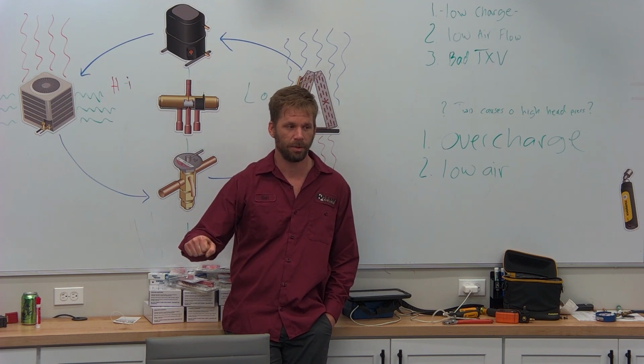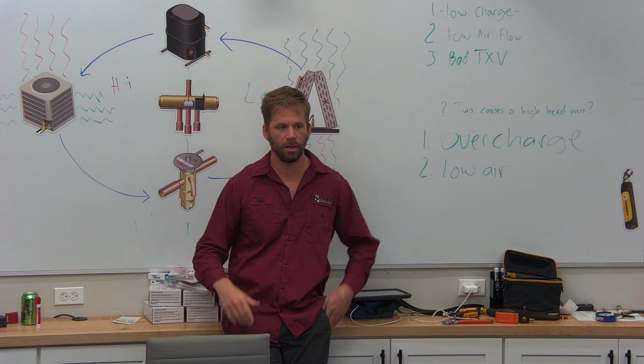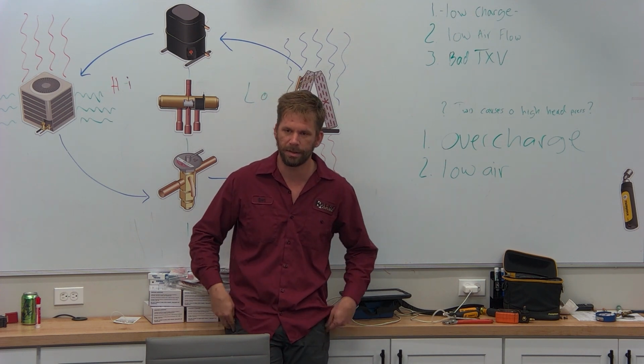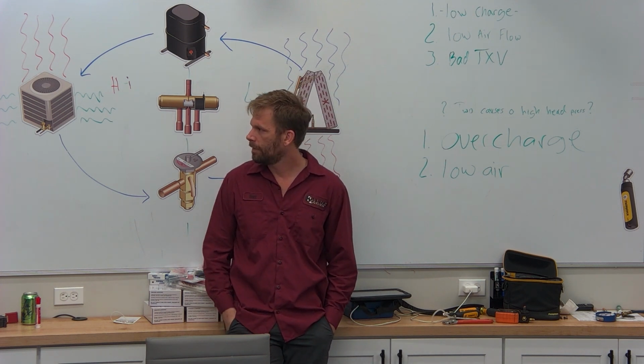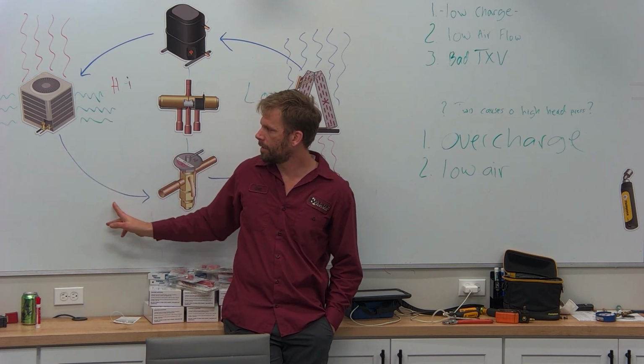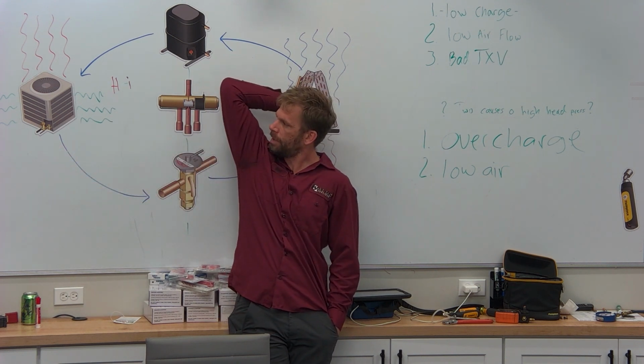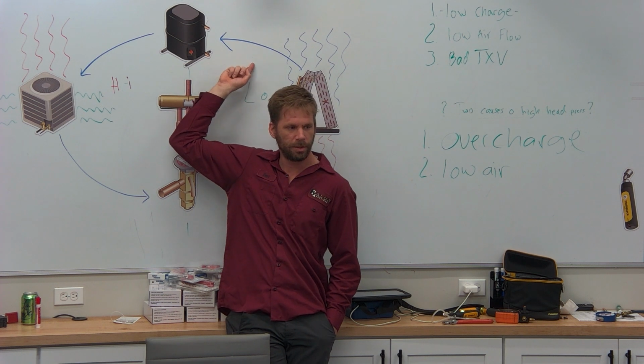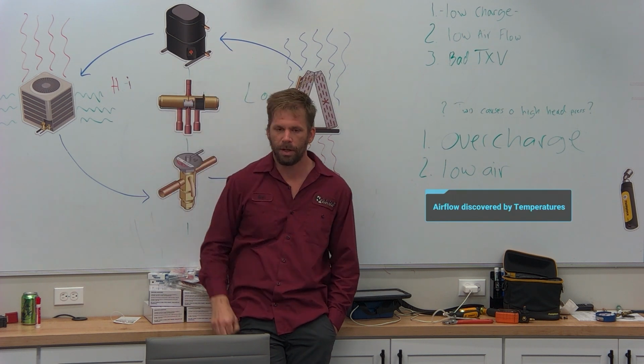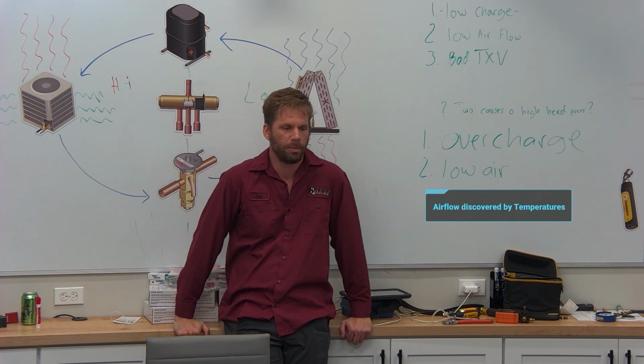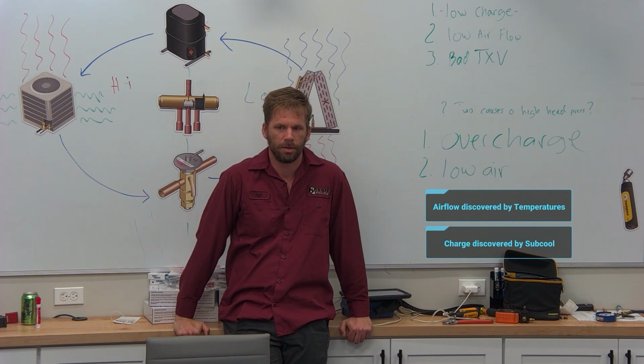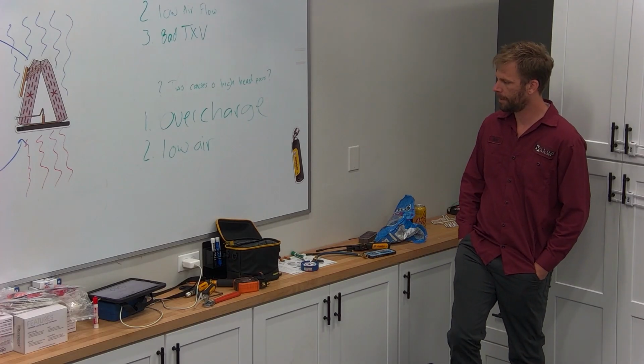That's pretty hot liquid line, holy cow. Very inefficient condenser coil. What do we got going on here? So let's give this thing a wash. It might look perfect, but it's probably internally packed. And so if it's not getting rid of its heat, we're gonna have a higher temperature. If it's not picking up its heat because of airflow, we're gonna have a colder temperature. Airflow is discovered by temperatures. Refrigerant charge is discovered by subcool. All right, that was a lot.